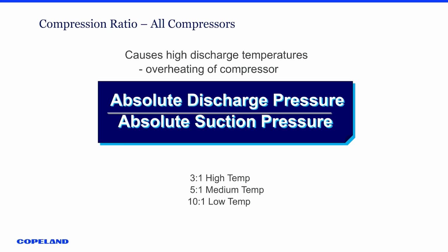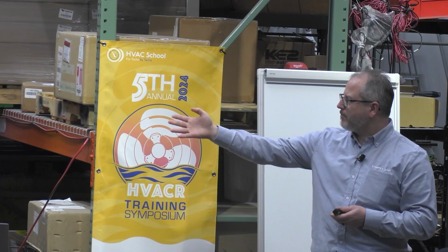All right, now we're going to get into compression ratio. So we're going to make this really easy. All we have to do is take our discharge pressure and our suction pressure. We're going to add 15, 14.7. For easy math, we're going to say 15. Okay? And then we're going to divide those. So whatever you have, you're going to take the high side divided by the low side, and it'll come up with a number.